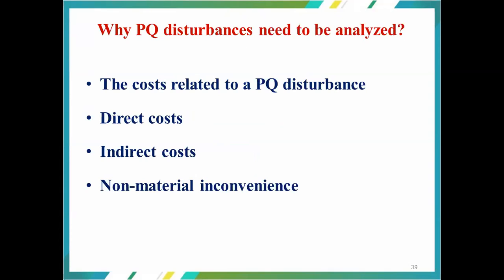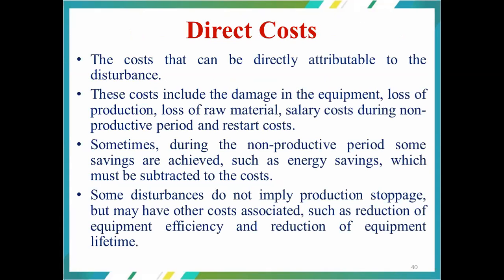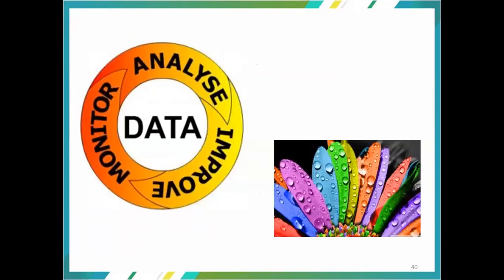So power quality disturbance needs to be analyzed, because the costs related to power disturbances are very high. There are two types of cost: one is the direct cost and the other the indirect cost, and the third one is the non-material inconvenience. The direct cost is related to the loss of production, or the loss of raw materials, or the loss of lives, or loss of materials, etc. And sometimes it may result in poor efficiency also. So when it comes to power quality, we are supposed to capture the data with data loggers, maybe a power quality analyzer or power quality data loggers, wherein we continuously monitor and analyze the data, and wherever possible we improve it, and thereby we improve our operating efficiency also.